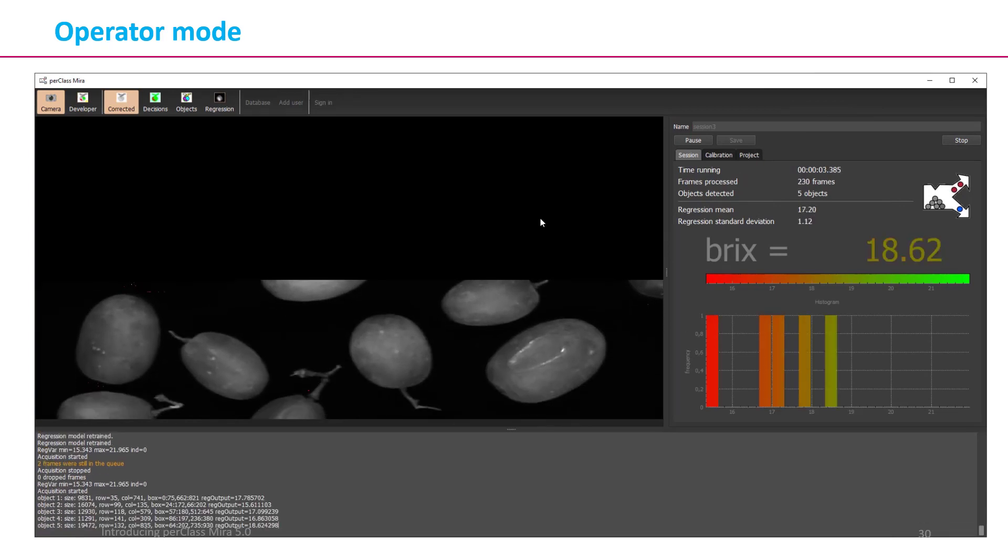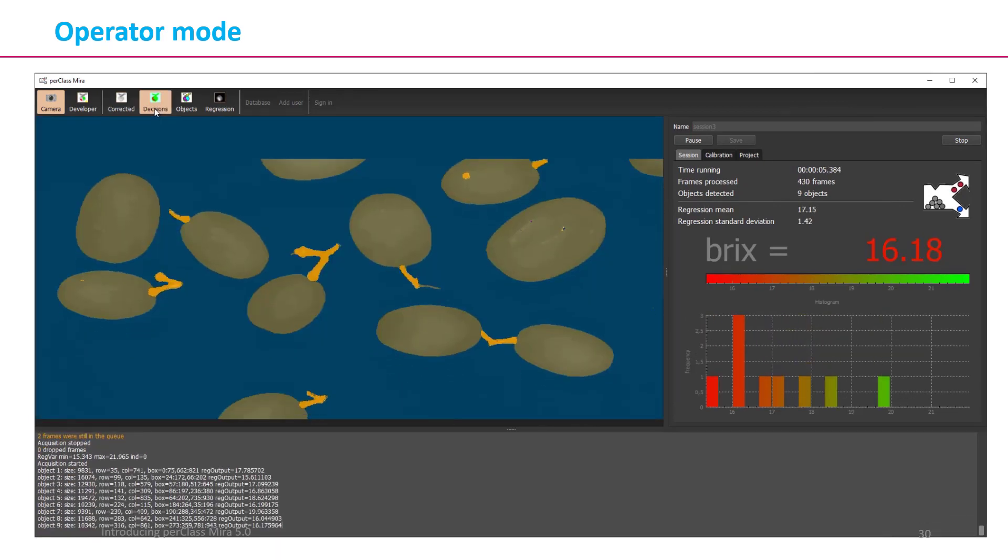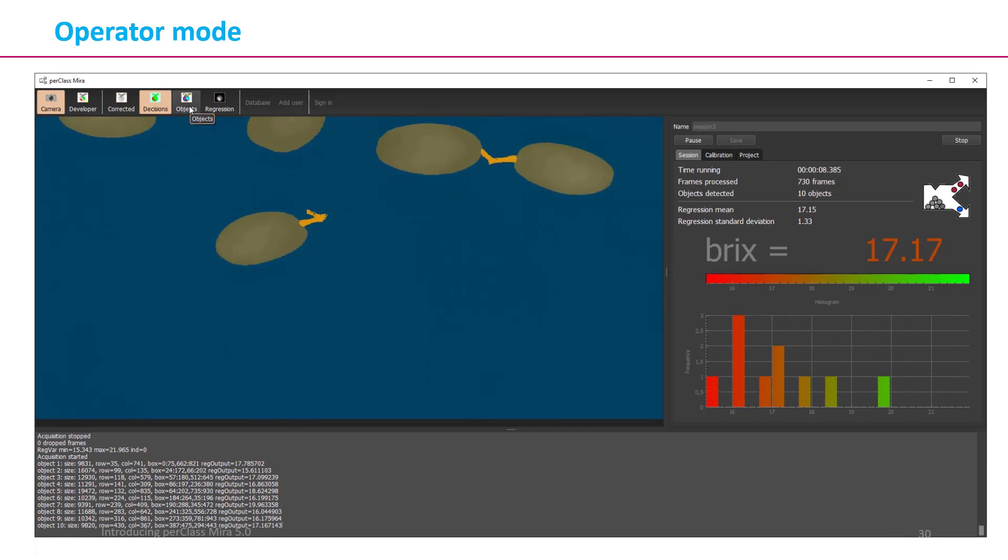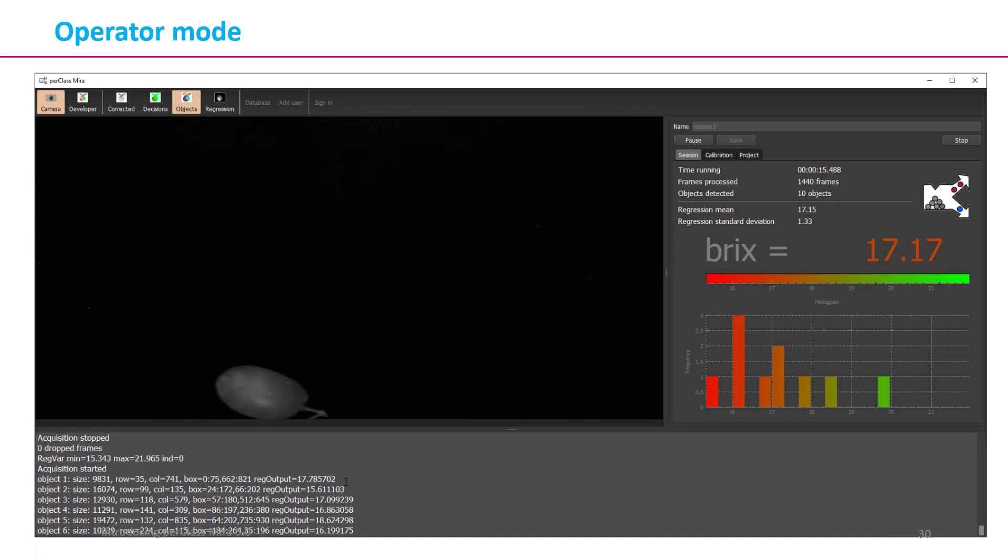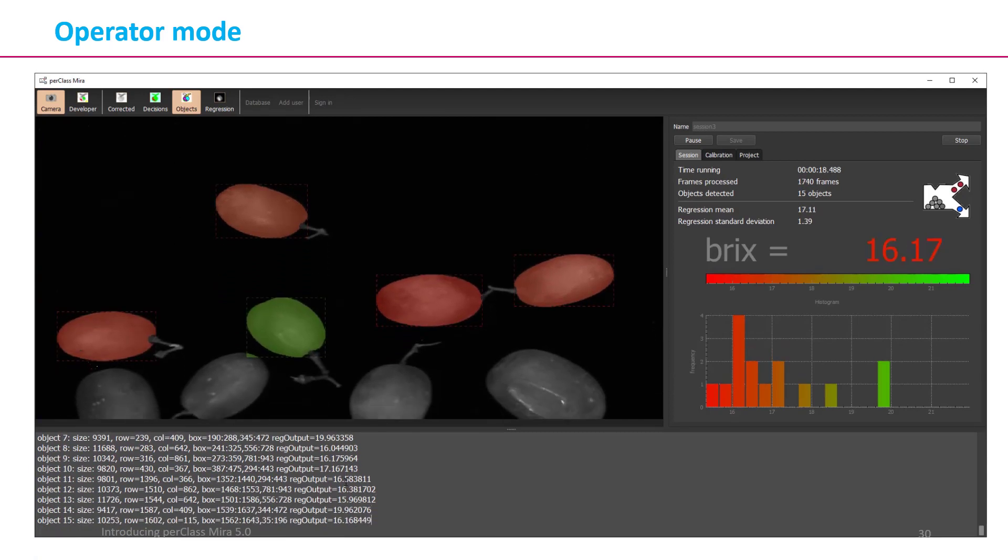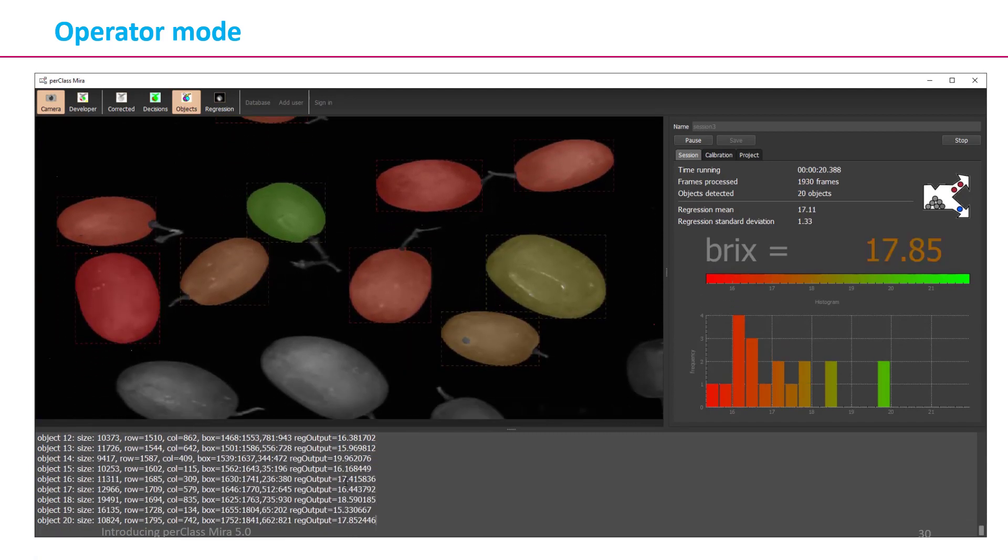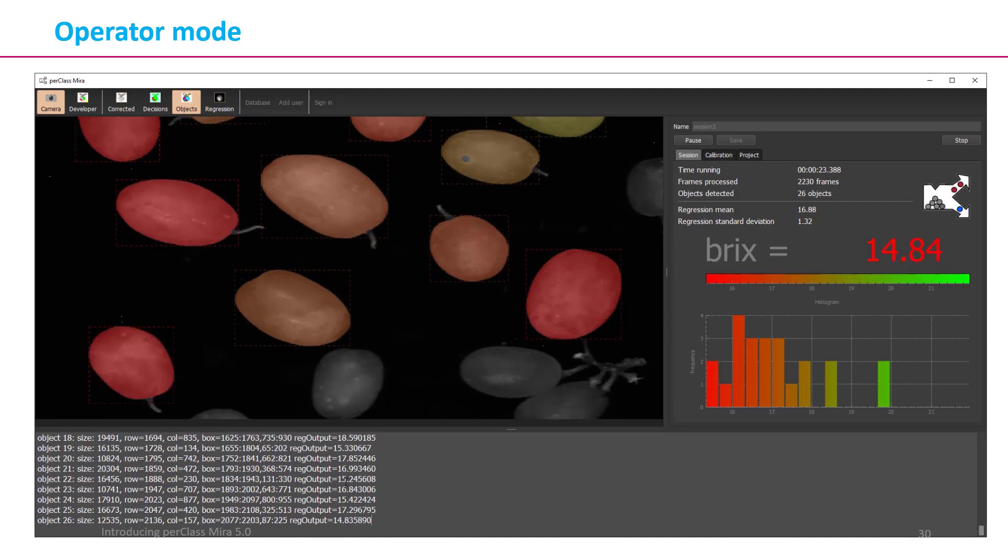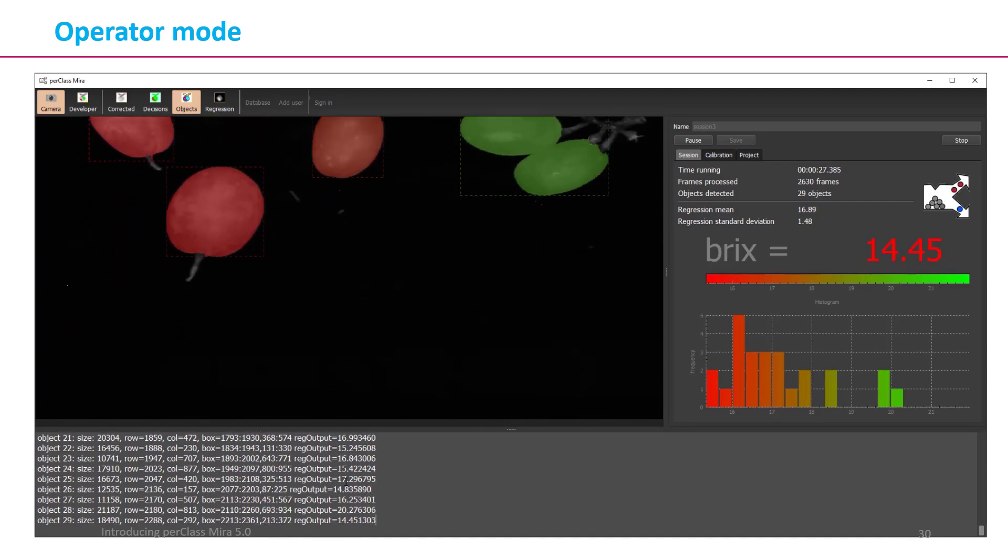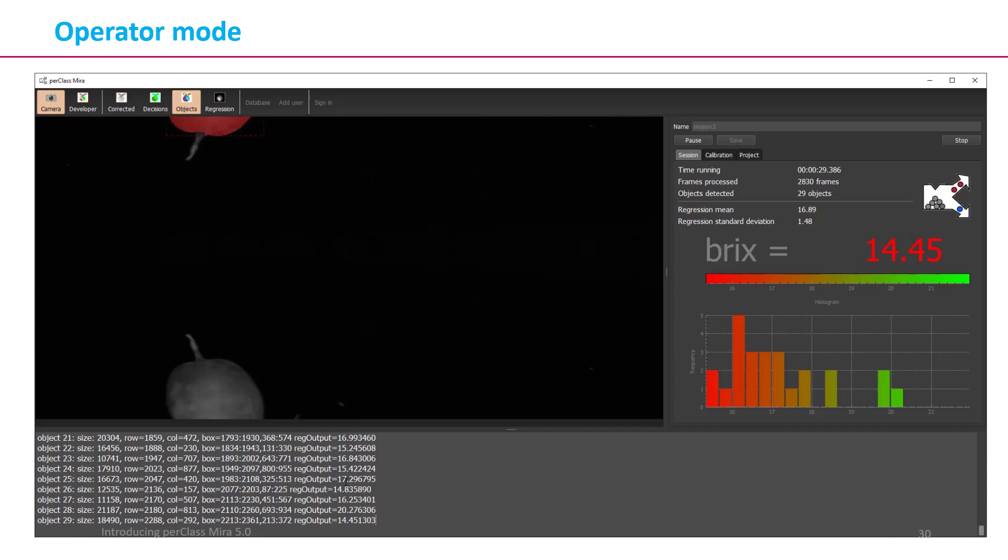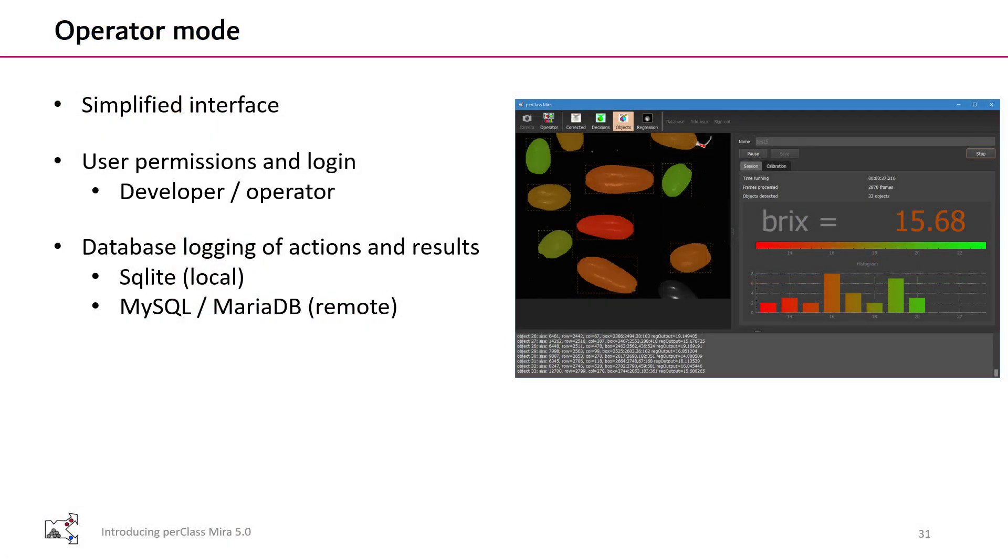Which is a very simple interface session oriented. So we start a new session. Here we can see the data flowing in reflectance, per pixel decisions. And we can switch it into per object mode. So when operator puts the new product on the stage, what we can see is the Brix value per object, but also the object counts, mean, standard deviation and the histogram. So this is a simple tool to perform incoming goods inspection in lab or at line. The operator mode allows to distinguish developers who can change models from operators who can only apply the solution in the simplified interface.